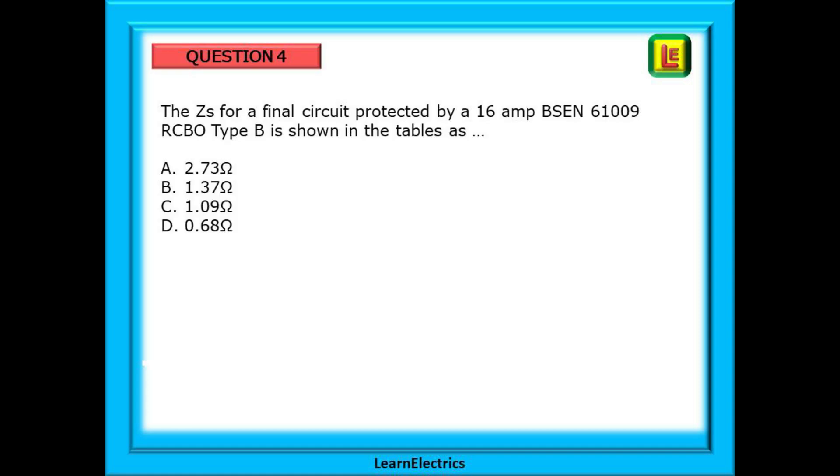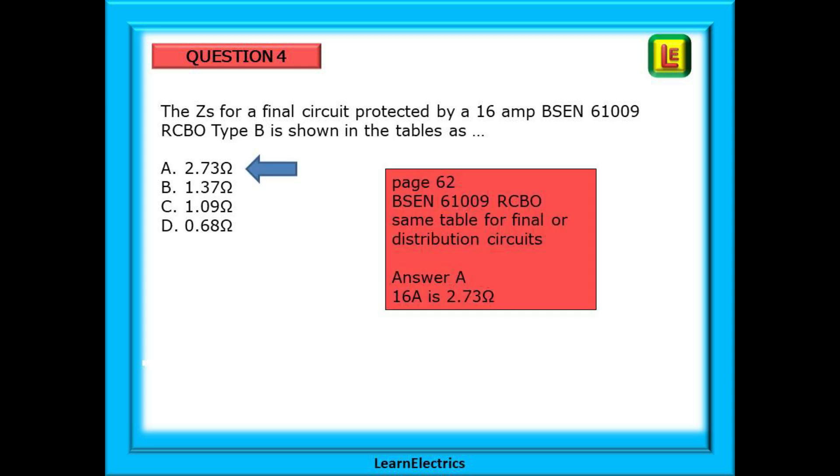Now, question 4. The question asks: the ZS for a final circuit protected by a 16-amp BS EN 61009-RCBO type B is shown in the tables as... Again, pause the video, find the answer and continue. This time, it is answer A, 2.73 ohms.